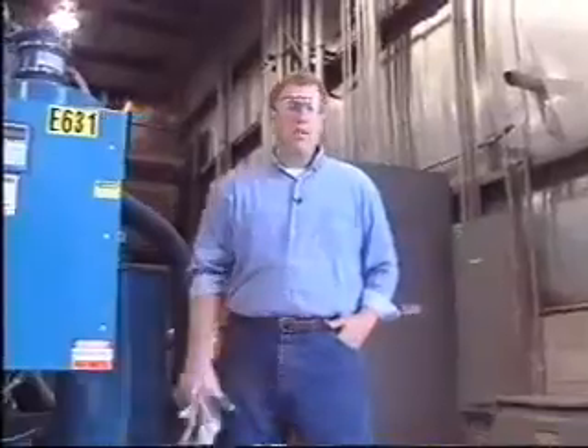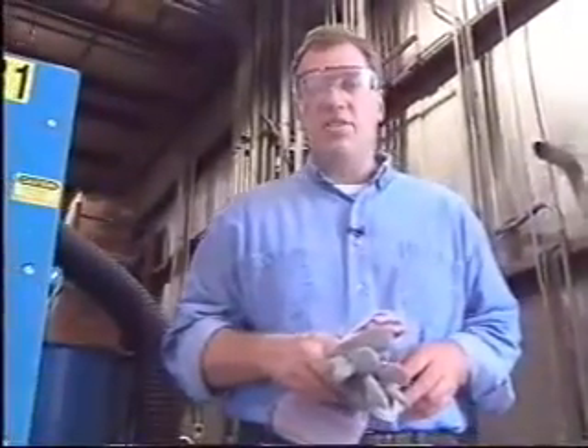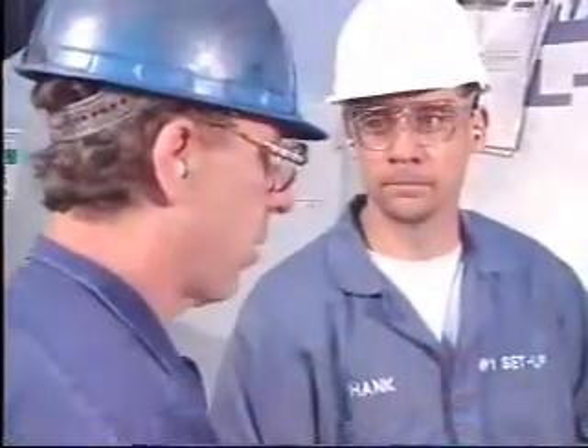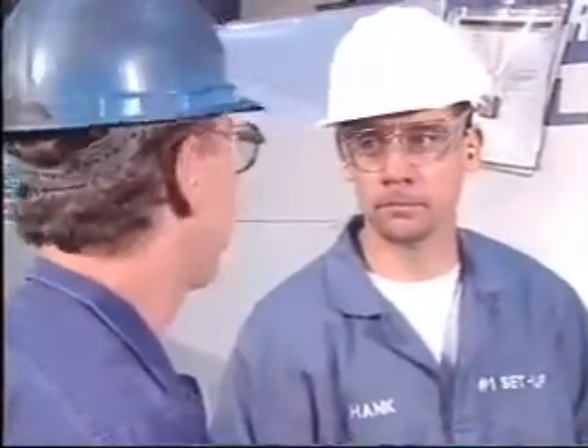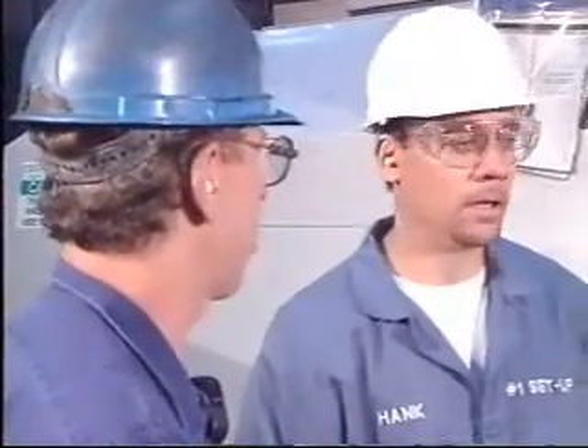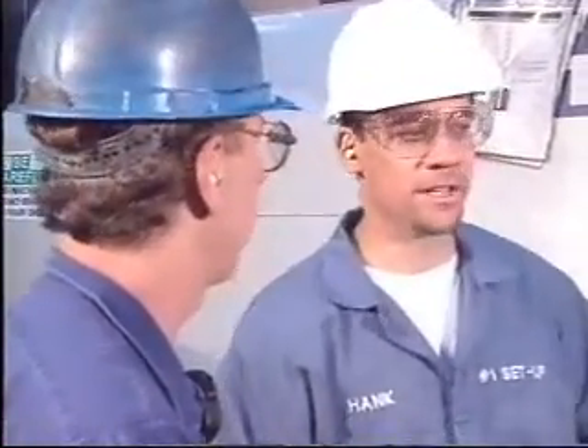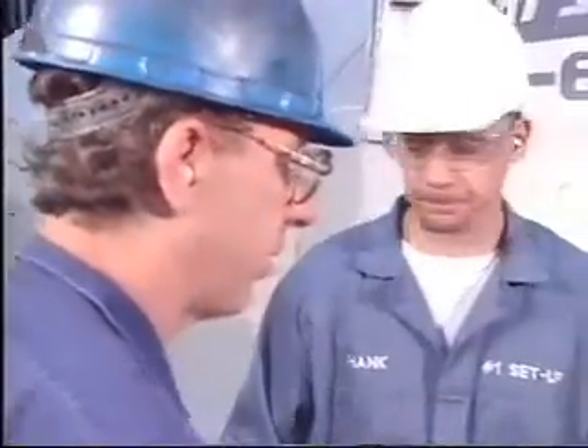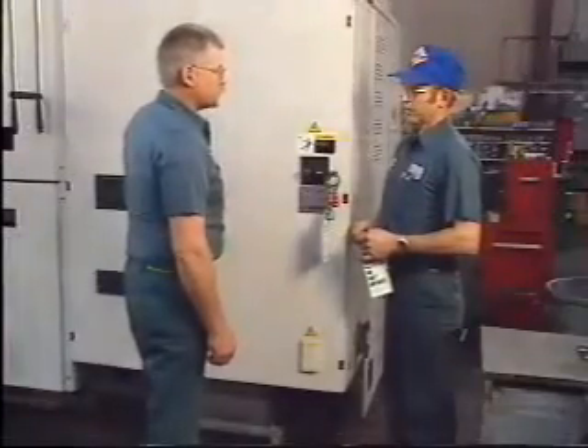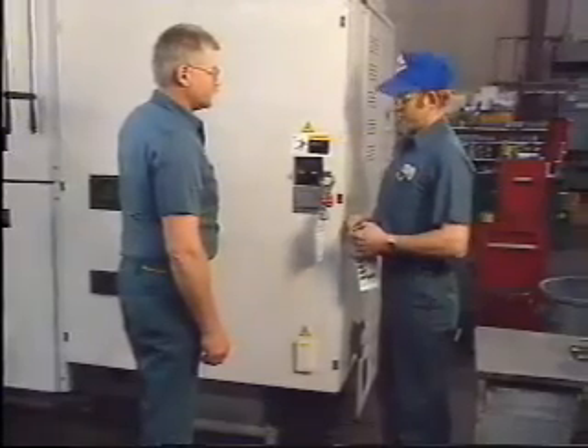There are just a couple of other things to keep in mind about the lockout-tagout rules. One has to do with what happens at the end of a shift. A high percentage of accidents happen just after shift changes. It's often due to a lack of communication. That's why you should try to meet at the lockout-tagout device with the person you're relieving. And then before you leave, meet with the person who's relieving you.